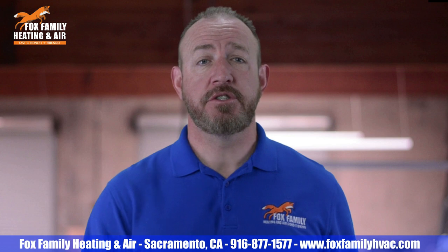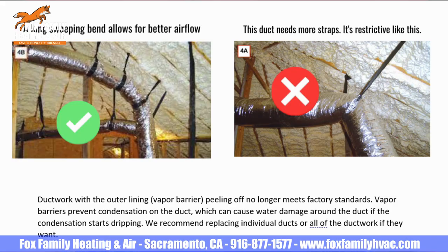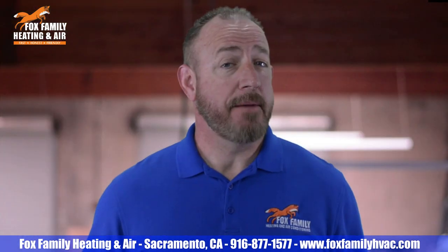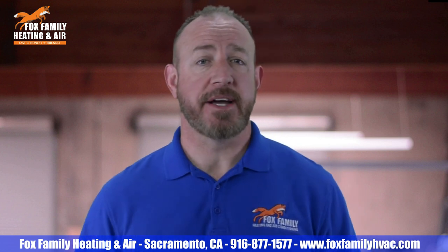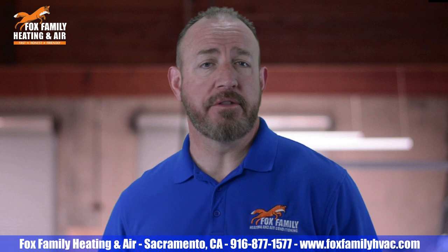Check the design and flow of the ductwork. Are the ducts strapped or lying on the attic's joists in a straight line? They should be run with long bends, as opposed to short bends — you're trying to avoid having a duct that looks like a roller coaster going up and down and twisting all over the place. The path of least resistance is the most efficient way for air to travel through ductwork. It's not necessary to change your ductwork every time you replace your HVAC system, but if it's older than 30 years, it could be time to start thinking about it.